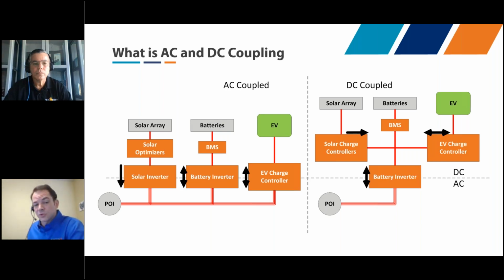Beside that, we've got storage: batteries protected by a battery management system, going through a bidirectional battery inverter, because it can both charge and discharge the battery, connecting onto the AC grid. Beside that, we've got an electric vehicle going through an EV charge controller, typically pulling energy from the AC bus and charging the electric vehicle. If it's a vehicle-to-grid application, that can also be bidirectional. That's called an AC coupled system because all of the different sources of energy and loads all connect together on the AC bus.